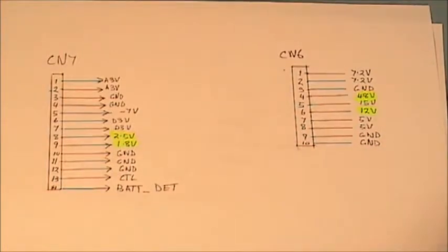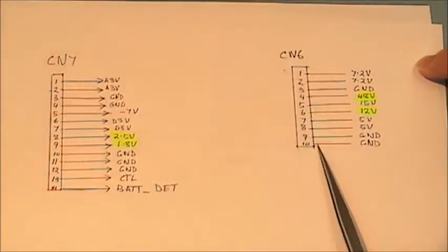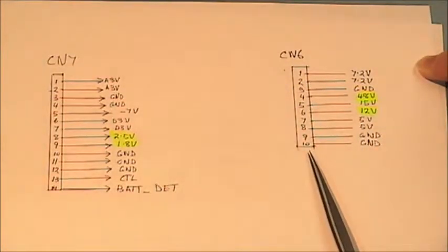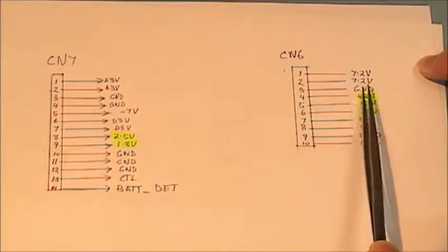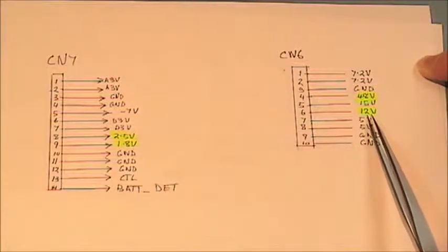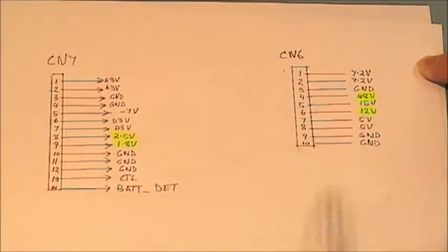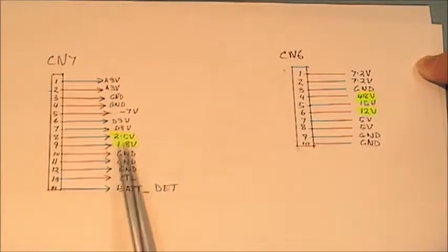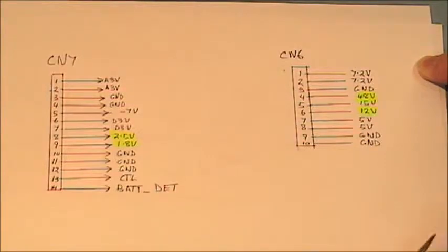Here is a diagram of the pin outs on the connectors of the power supply. I am just showing you these two connectors because this is where I had the problem. On CN6 we have 10 pins and our 48 volt supply, 15 volt supply and 12 volt supply were all missing. And over here on the CN7 connector, our 2.5 volt and 1.8 volt was missing from the CN7 connector.